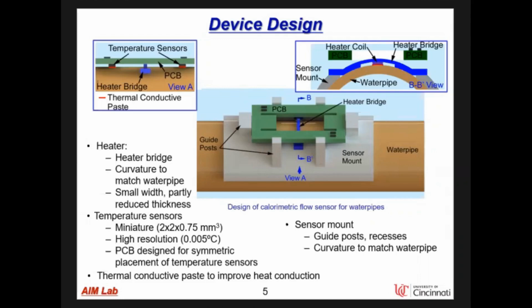As shown in view A from the side, miniature temperature sensors with a high resolution of 0.005 degrees Celsius are symmetrically mounted on the PCB. The sensor mount includes guideposts and recesses for precision in sensor components to achieve symmetric placement of temperature sensors relative to the heater coil. The sensor mount also has a curved contour matching the water pipe for easy deployment of the sensor. A thin layer of thermal conductive paste is applied on the heater coil and temperature sensors to improve heat conduction with the pipe.